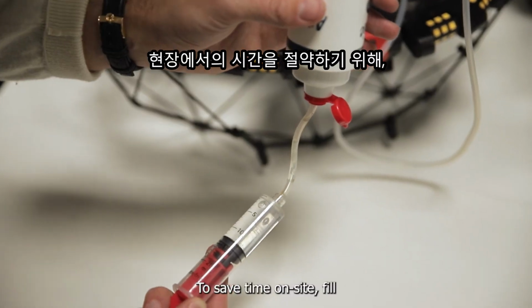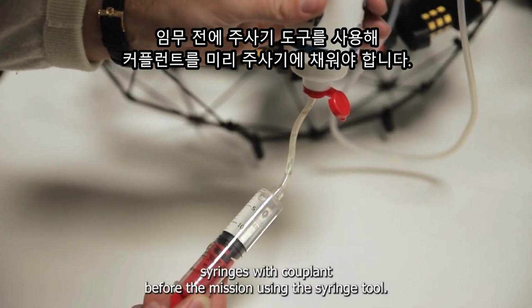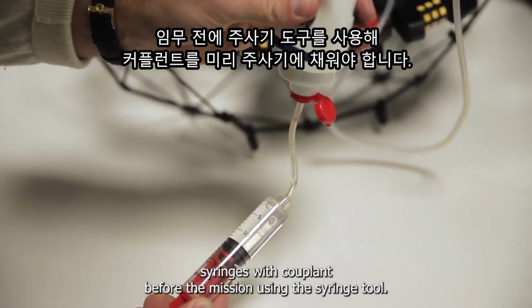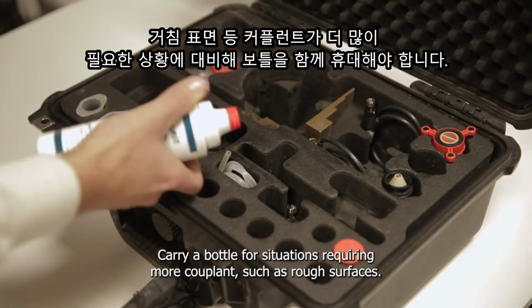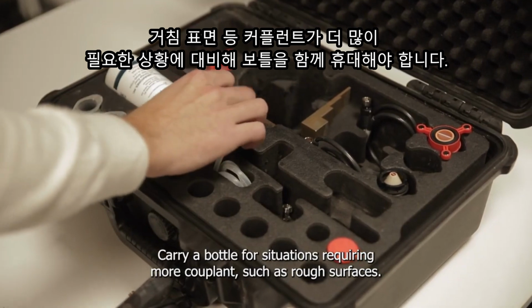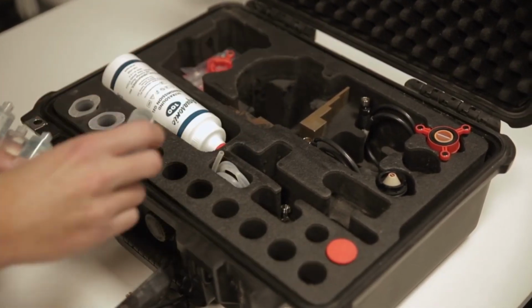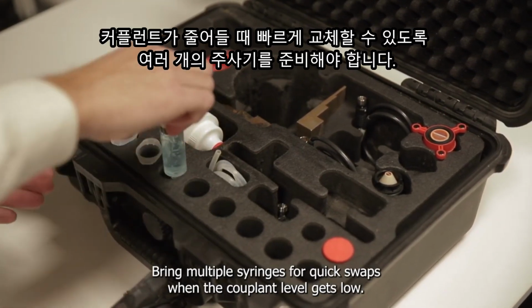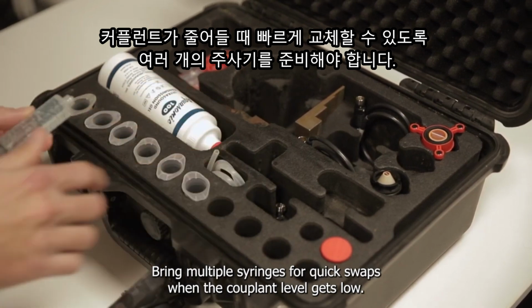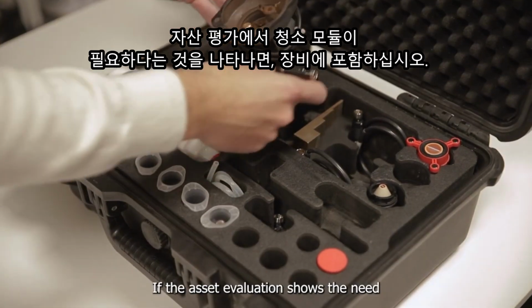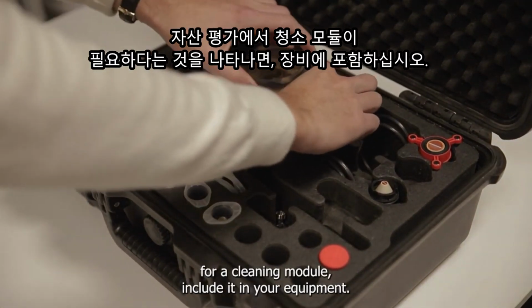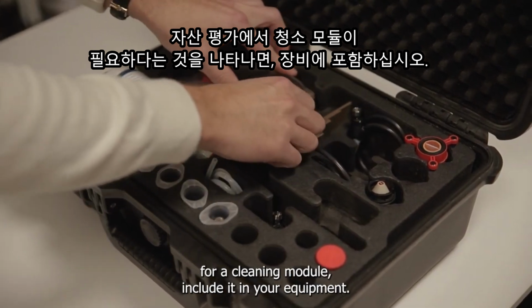To save time on site, fill syringes with couplant before the mission using the syringe tool. Carry a bottle for situations requiring more couplant, such as rough surfaces. Bring multiple syringes for quick swaps when the couplant level gets low. If the asset evaluation shows the need for a cleaning module, include it in your equipment.